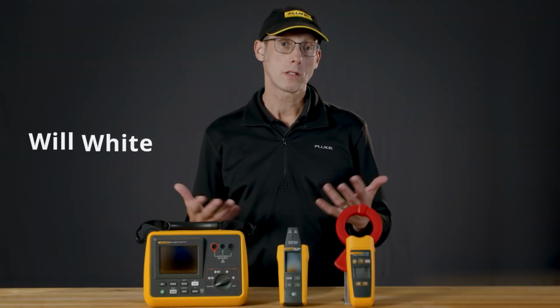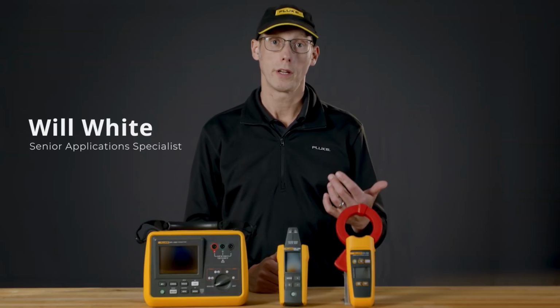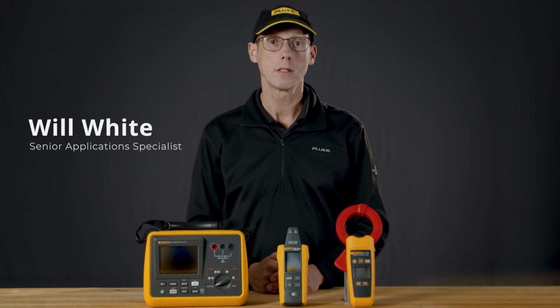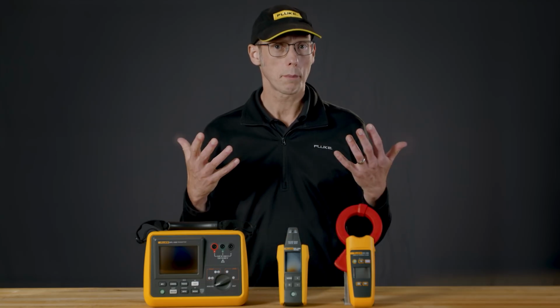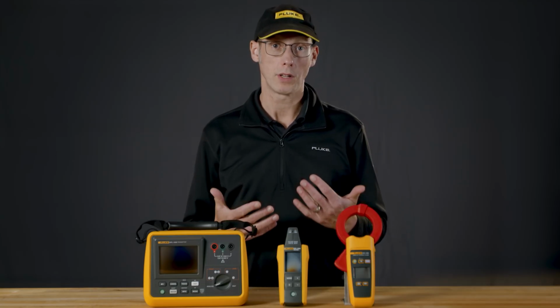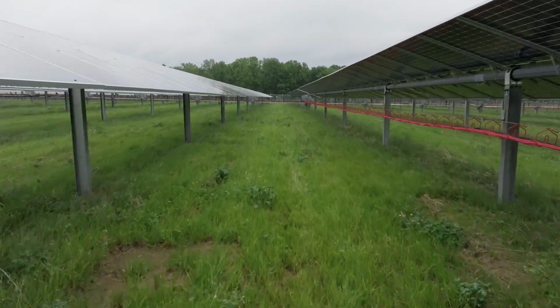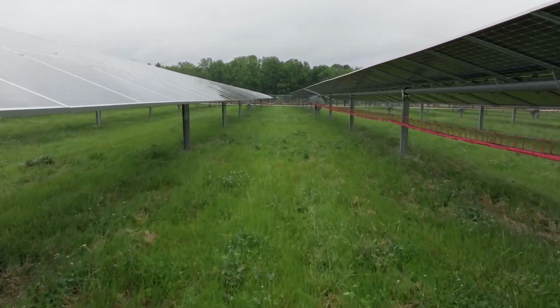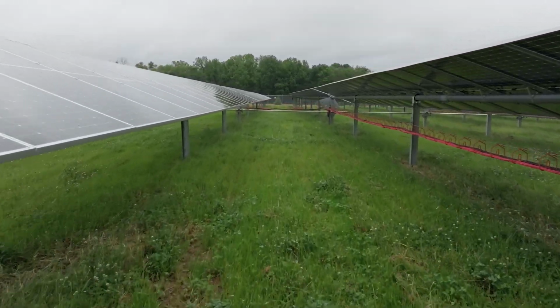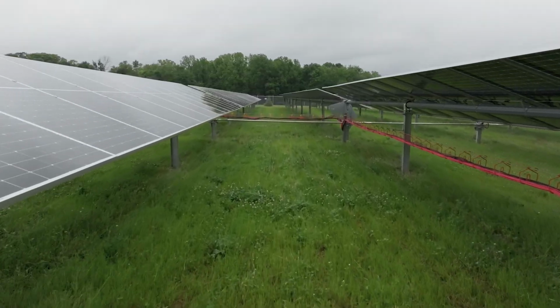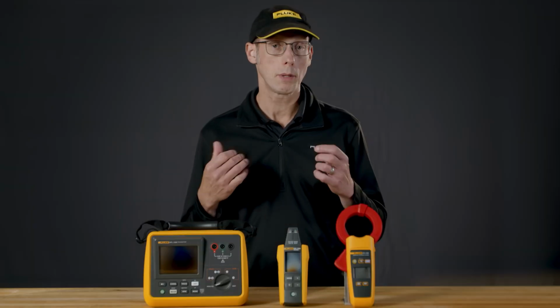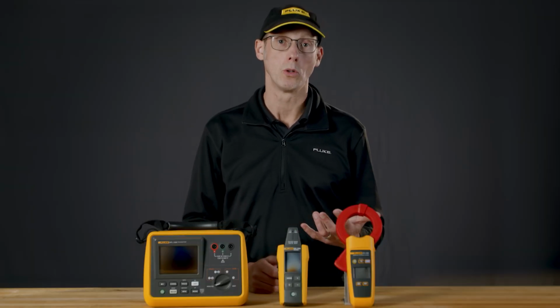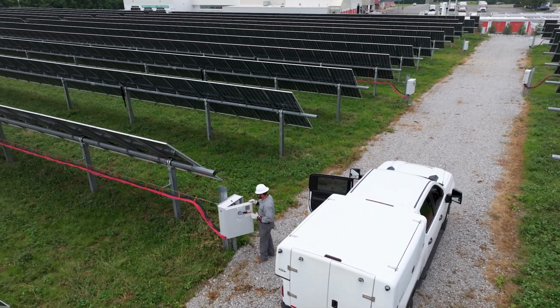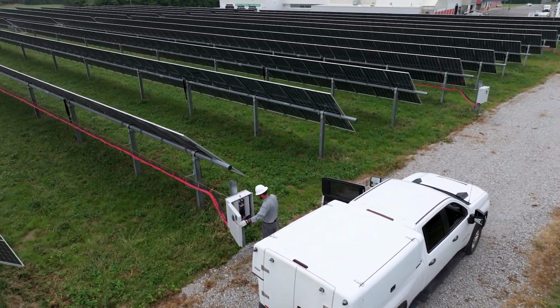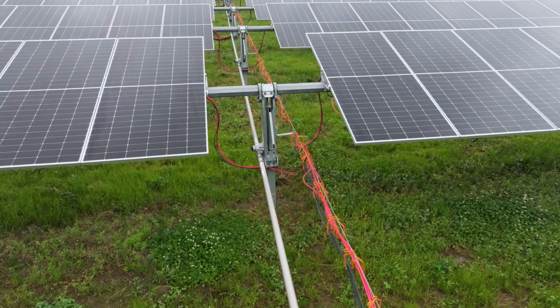Ground faults are a pervasive problem in solar installations, especially in our DC arrays. But let's talk about the basics of what a ground fault is. A ground fault is an unintentional connection between a current-carrying conductor, like our DC positive or negative, and a grounded metal part. And that could be anything from the frame of a module to the racking, maybe it's inside of a combiner box or an inverter, or in metal conduit.